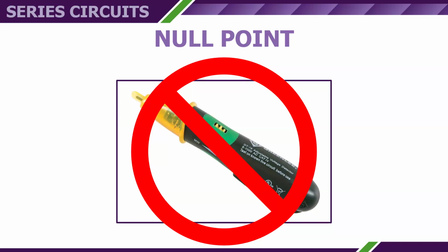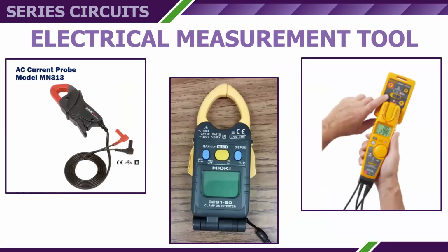But it will not pick up all points in the Airfield lighting series circuit. There's a null point in there. So do not rely on these to tell you that the Airfield lighting series circuit is de-energized. Always use a true RMS ammeter to determine if an Airfield lighting circuit is energized or de-energized.